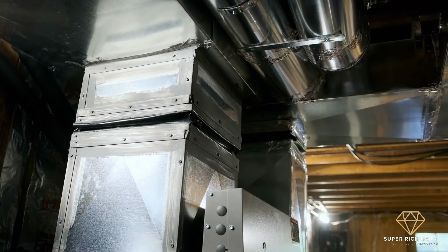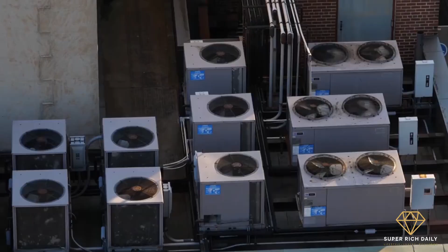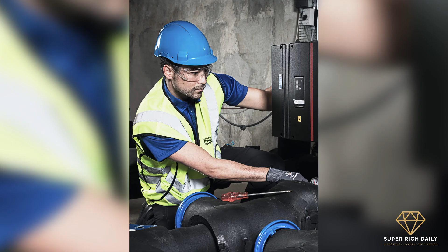Grundfos recommended changing to close-coupled end suction pumps with variable frequency drives, intelligent NBE pumps. These could provide the exact flow requirements to the chillers without wastage and improve the delta T to 5 degrees Celsius, a simple turnkey solution.